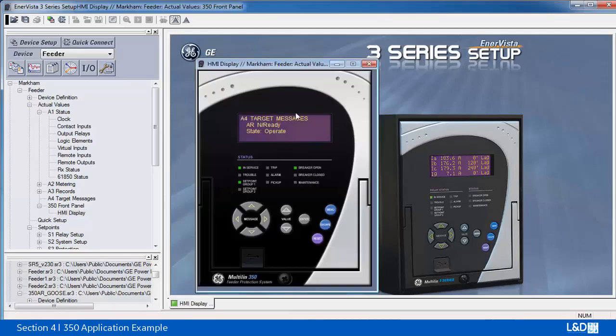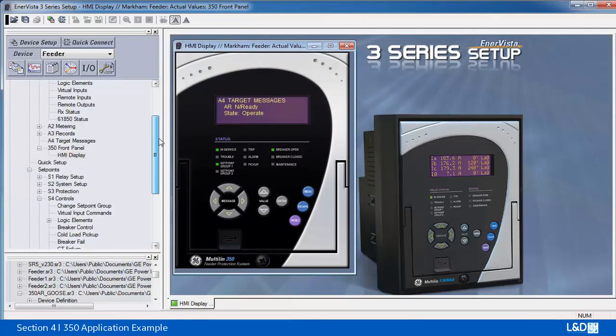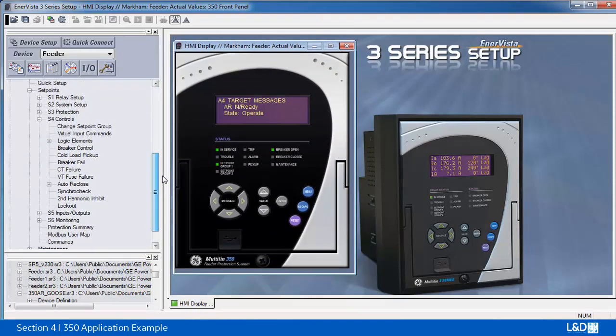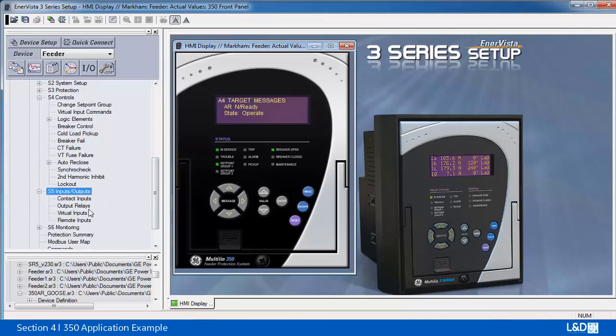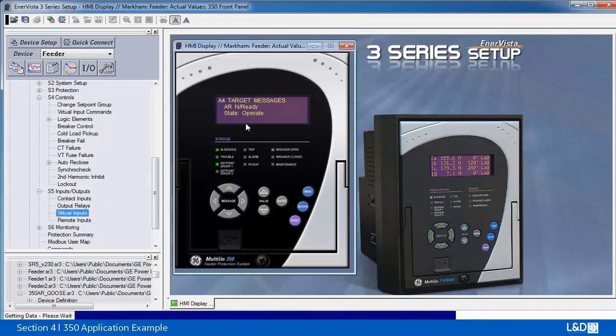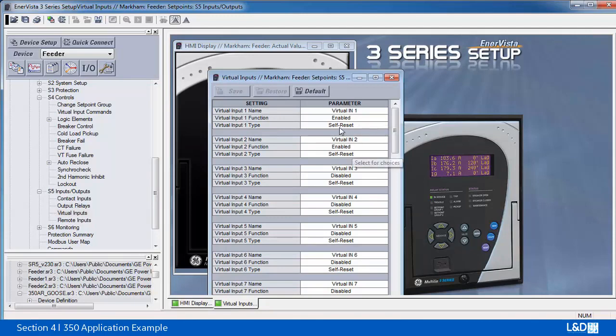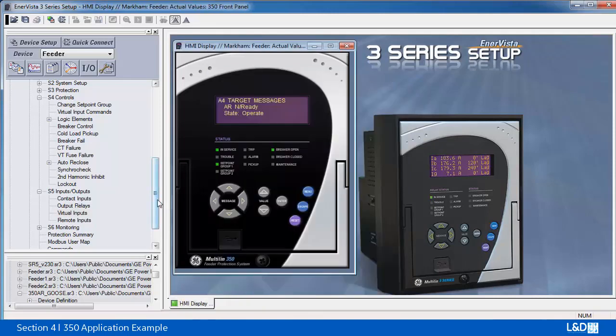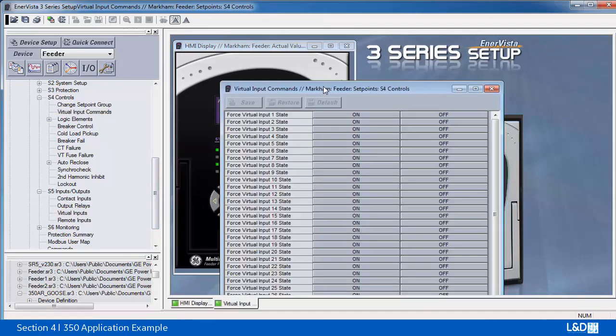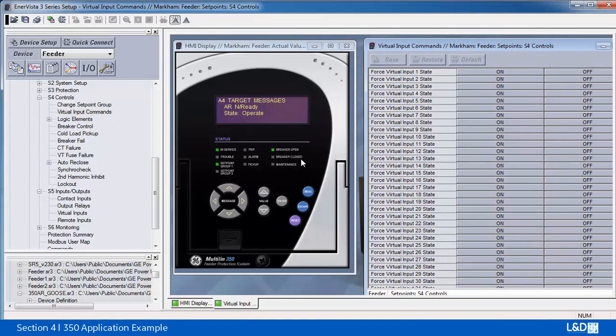So we see now the breaker is in open status. We can manually close the breaker by using virtual input 1. Virtual input 1 should be enabled. We enabled both 1 and 2, and be careful here, the setting is self-reset mode. We cannot use the latch mode. Now we're going to use the command under control, virtual input command. We're going to manually close the breaker, and this LED should turn on.